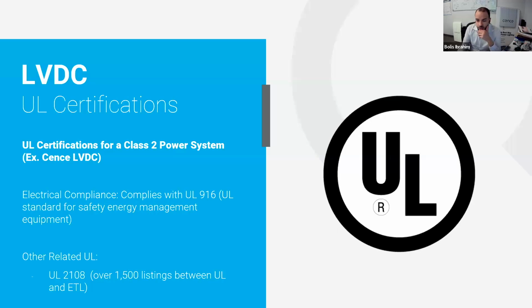The UL certifications you should care about in this type of system: there's UL 916, the standard for safety energy management equipment. And so our devices are UL 916. And a lot of devices on the market in this DC space will be UL 916. The other UL to care about is UL 2108. UL 2108 is the standard for low voltage lighting systems. That's for the lighting folks.